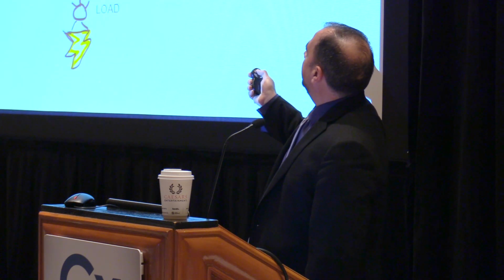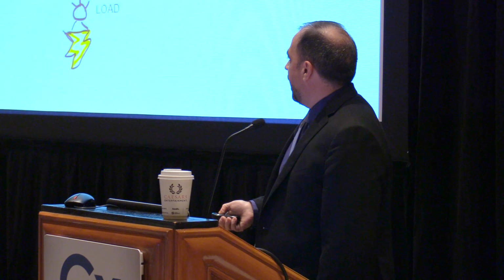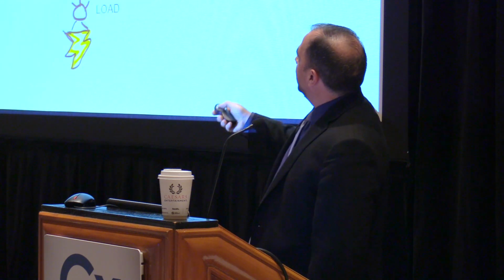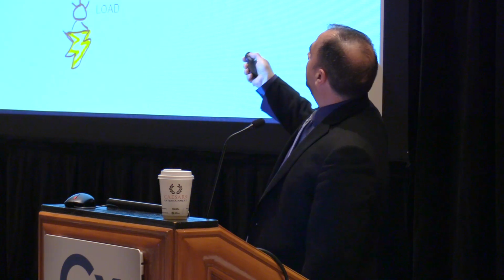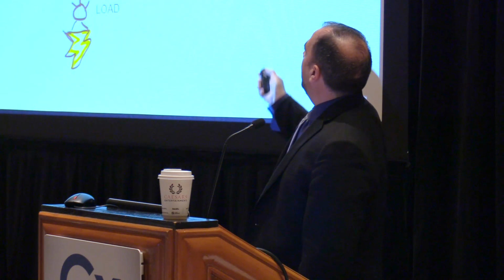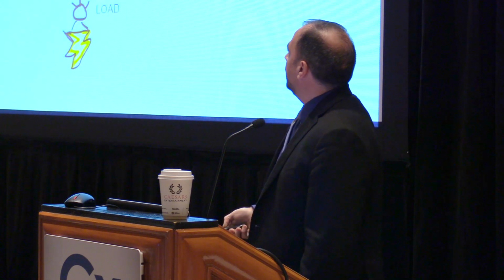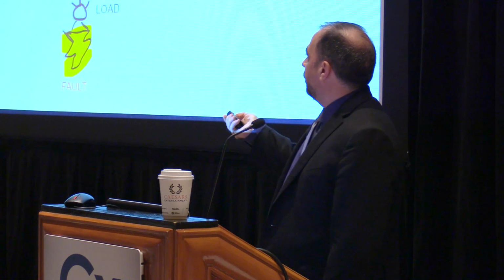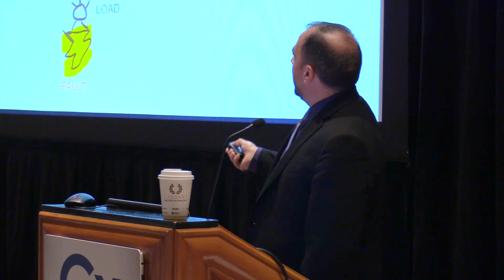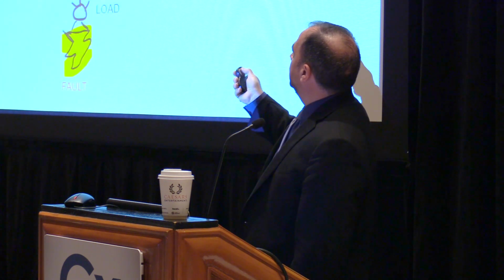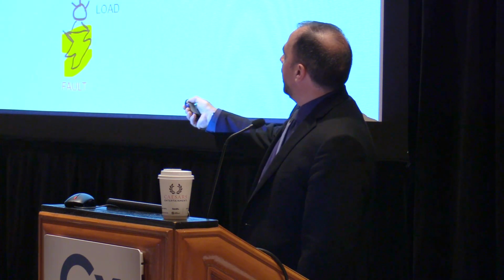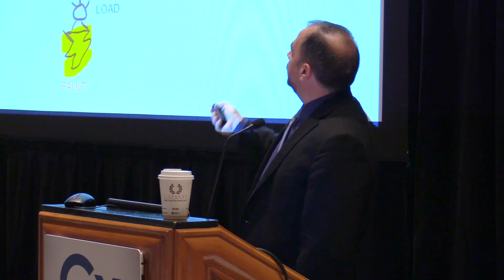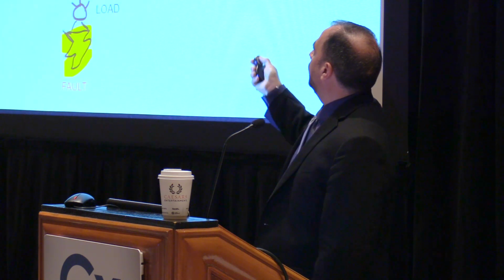So in this separately derived system, we've got the neutral and the ground bonded together here, so it's separately derived. If we have a fault, we've switched on the emergency side, and it goes through this way, and there's only one path for the fault to take, and the ground fault protection sees it all, and life is good. If we had a 3-pole switch on this system, there's actually 2 paths for the fault to flow, because we're connected over here, so it can take this path back over here to the source. So the ground fault protection on this side that we want to either alarm or trip isn't seeing all the ground fault, and it might not work. This is the short version, believe me.